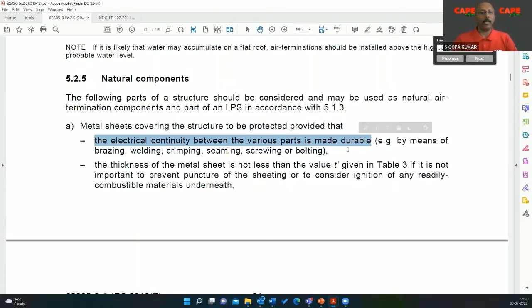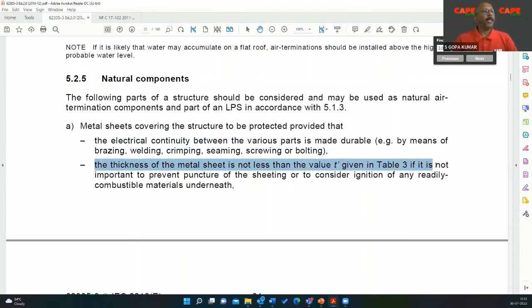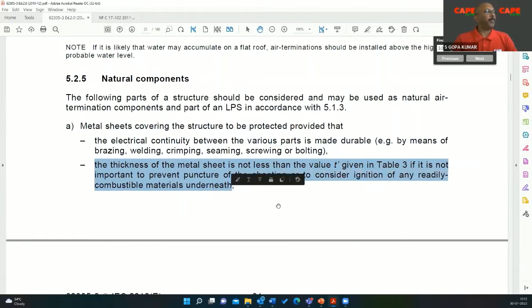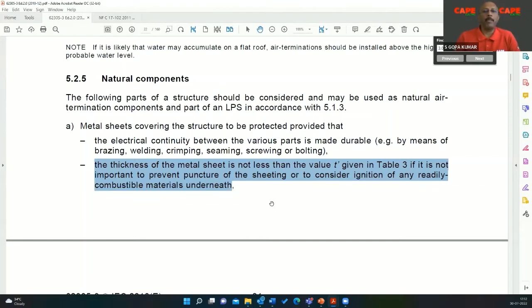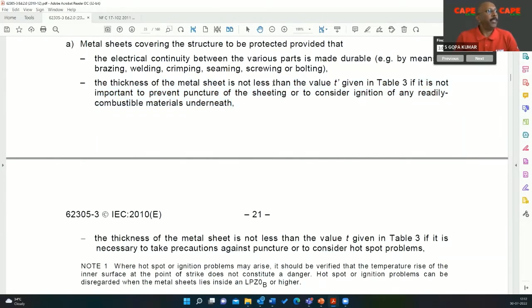We have to test and ensure that the continuity resistances are lesser. The thickness of the metal sheet must not be less than the value T given in table 3 if it is not important to prevent puncture of the sheeting or to consider ignition of any readily combustible material underneath. That means under the building roof, you may have explosives, people walking, a normal building, or a warehouse for steel, for example. The minimum thickness is necessary if you consider it is not important to prevent puncture.